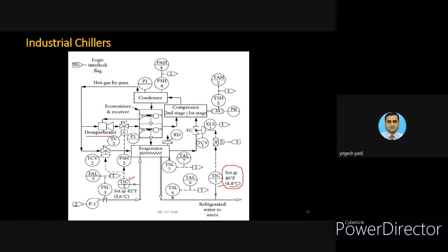And in the same place, limit switches are also connected. So what is the purpose of this XLS limit switch? That detects whether the suction vane is open or closed. If the suction vane is open, what action is taken, that is required to know. And when the suction vane is closed, what action is required.